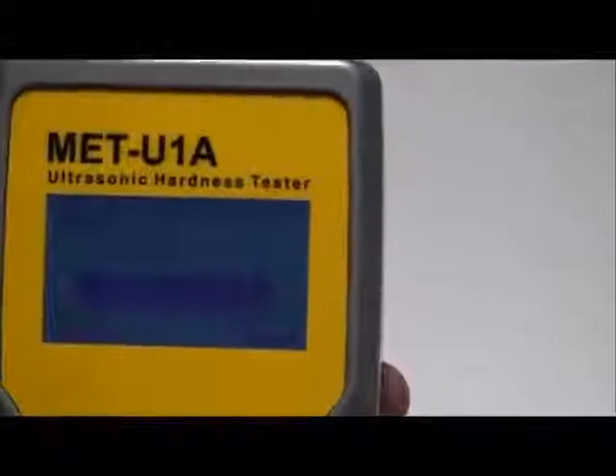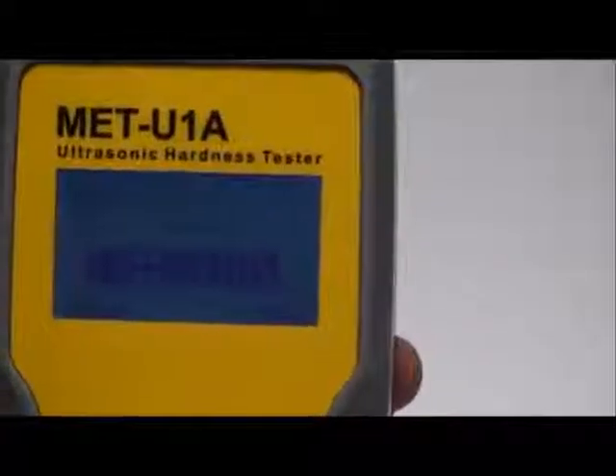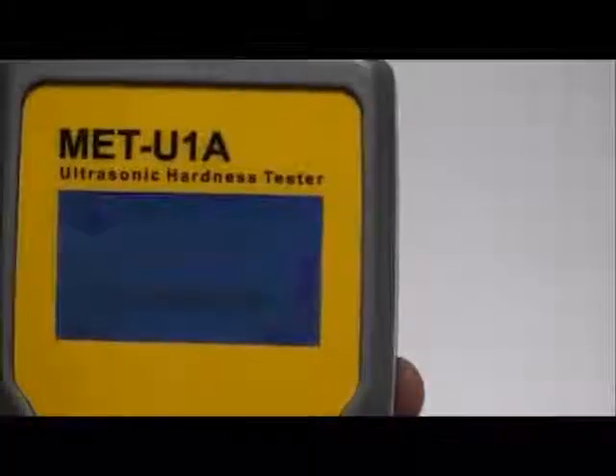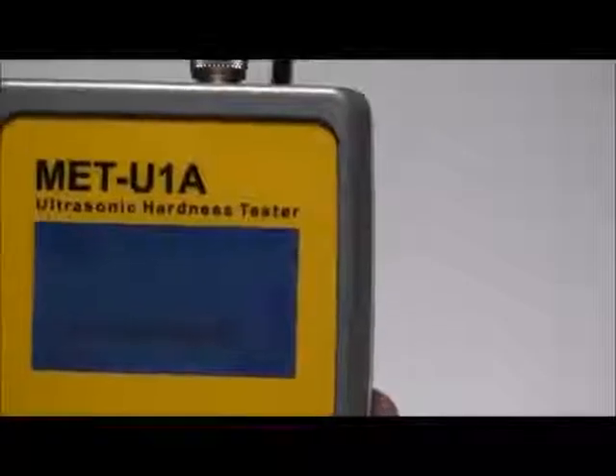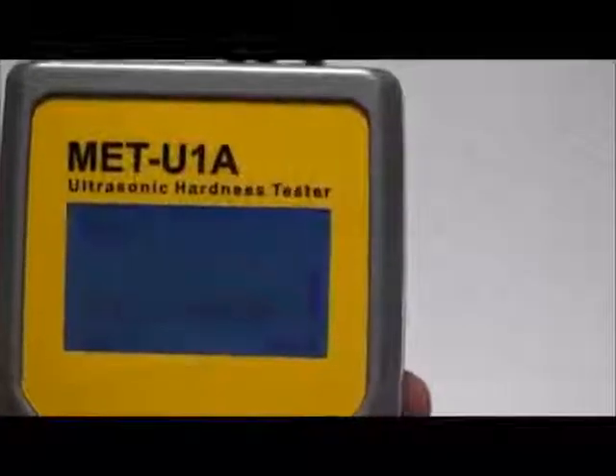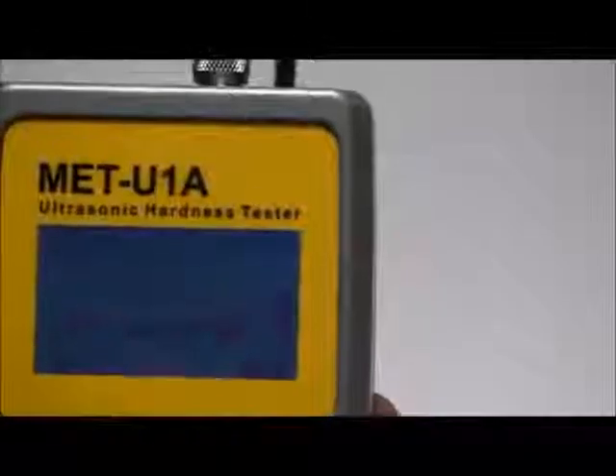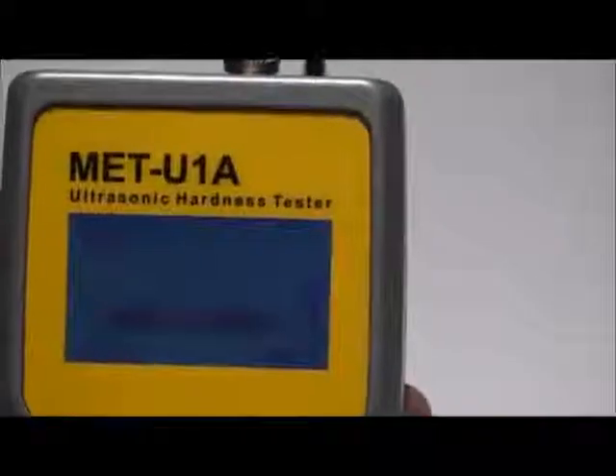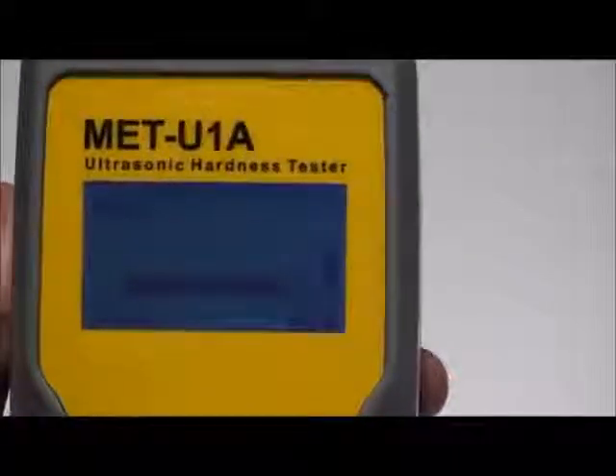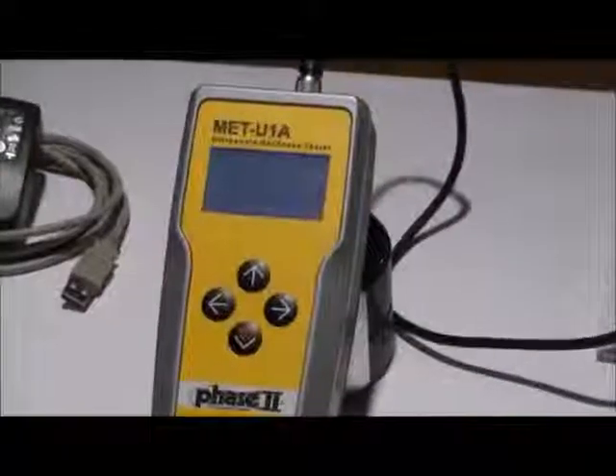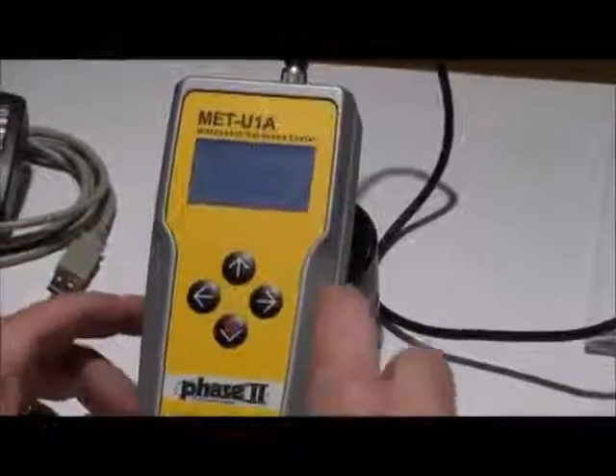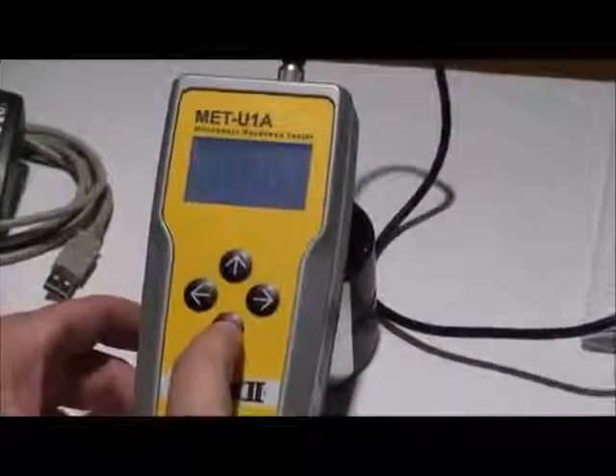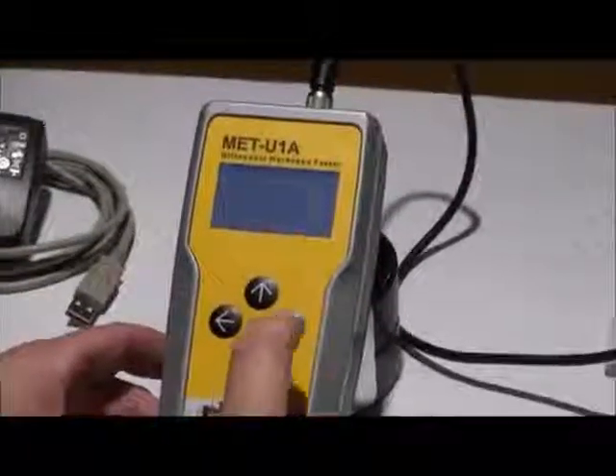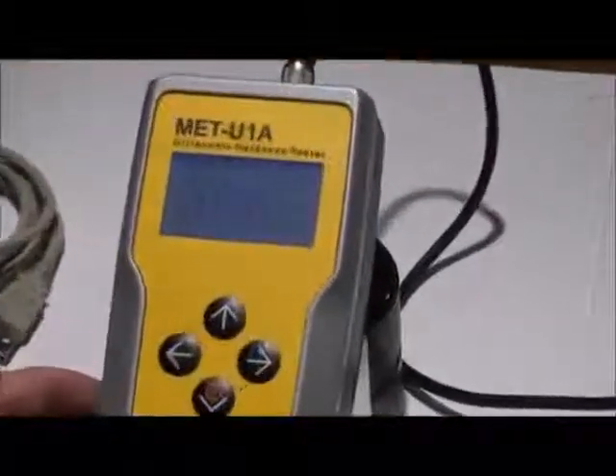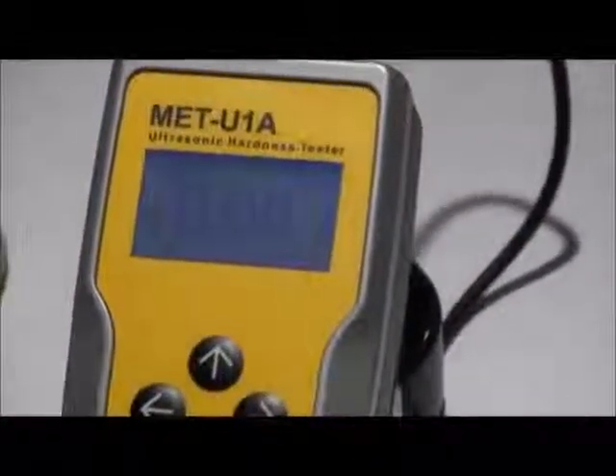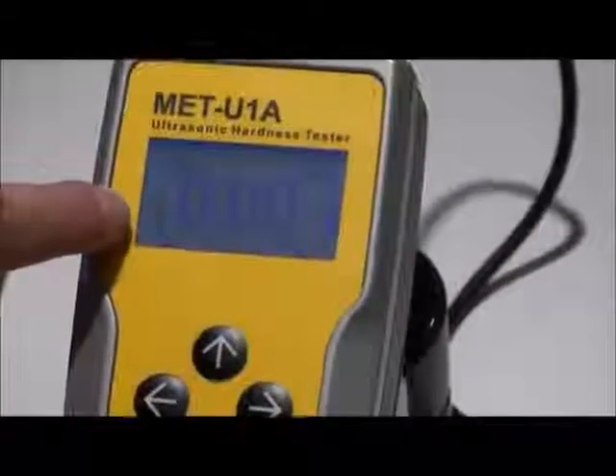Pressing the up arrow button any time brings you back to process in the blinking stage. Scrolling right again using right arrow button brings you to test. While blinking, press on the down arrow button to enter the test mode. You are now in archive test mode. Pressing the down arrow button activates the probe, puts you in measurement mode, and shows a flashing probe on the left of the screen.